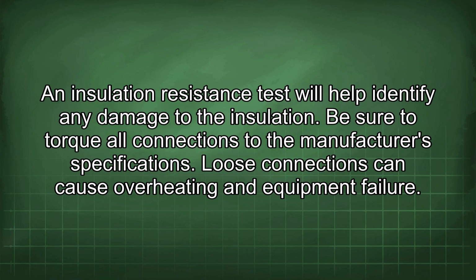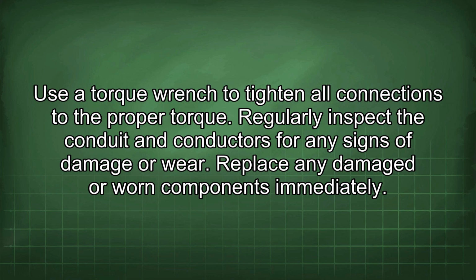Be sure to torque all connections to the manufacturer's specifications. Loose connections can cause overheating and equipment failure. Use a torque wrench to tighten all connections to the proper torque.